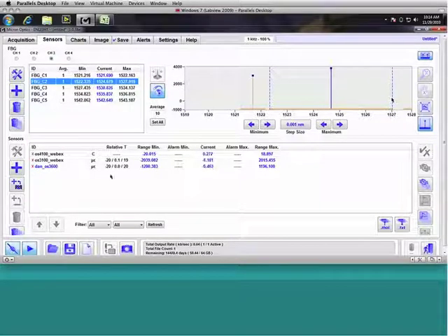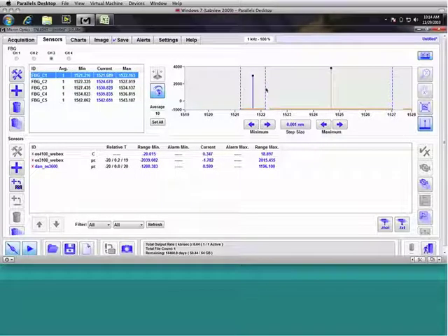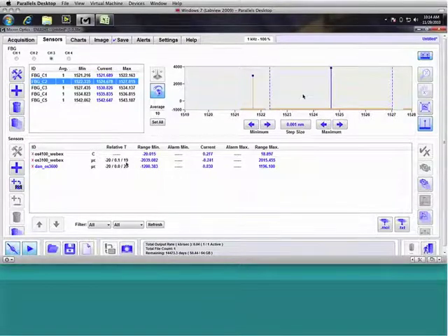So very quickly, we've established an OS3600. Wavelength ranges are provisioned for both the temperature sensing and strain sensing FBGs to operate from plus or minus 20 from ambient over a minus 1200 to plus 1200 microstrain range. I'd like to point out here the importance of the relative T column on the sensor grid.